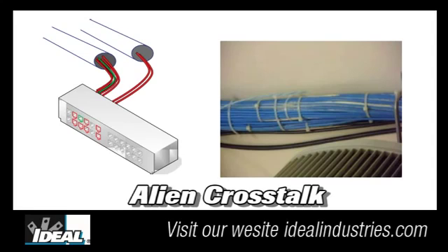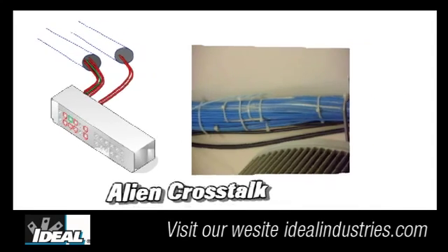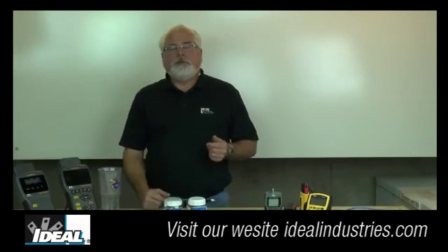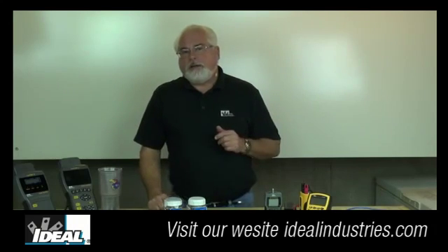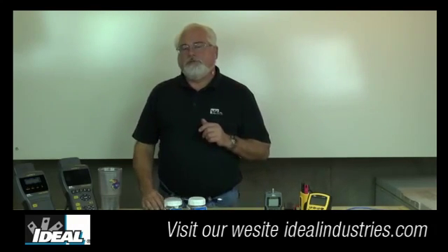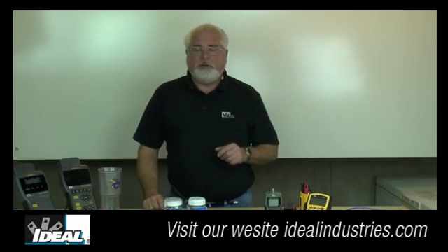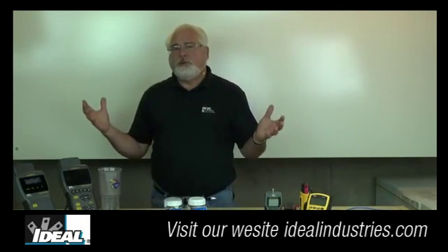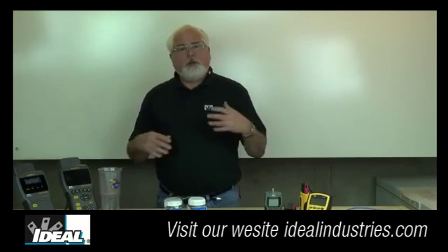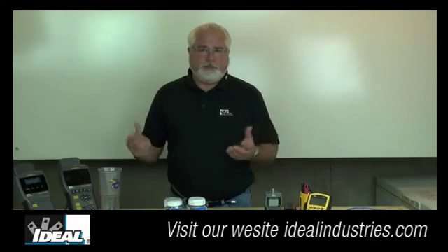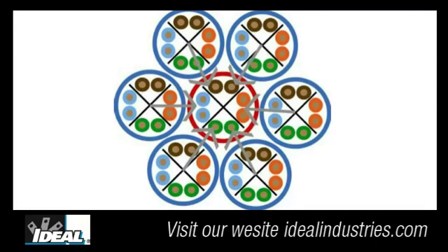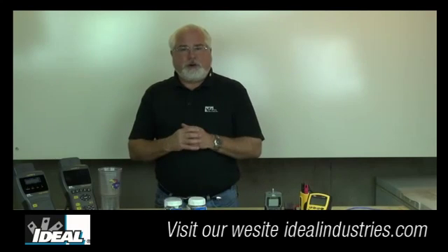And we can't do 100% alien crosstalk testing, and the industry does not require you to do it, but it is one more thing to look at if you're running into some cabling problems in your system. It's not quite functioning the way you need it to. And what we'll do when we do our certification testing, we'll identify some of what we call victim cables. And then when we do our certification testing, we will also do the test on the 6 cables right around that one and see what effect those 6 cables are having on our victim one, okay? And that is, again, called alien crosstalk.